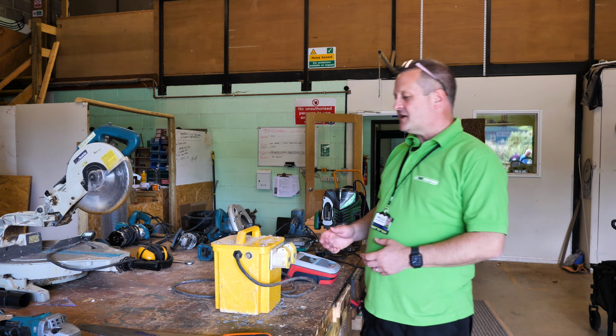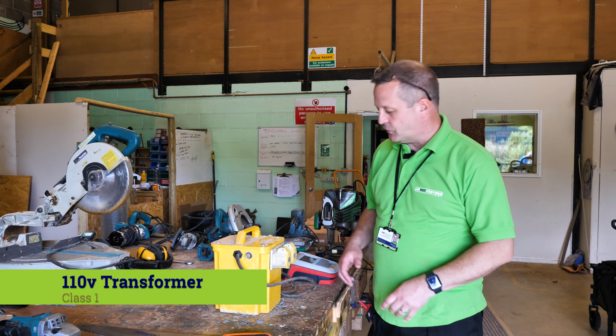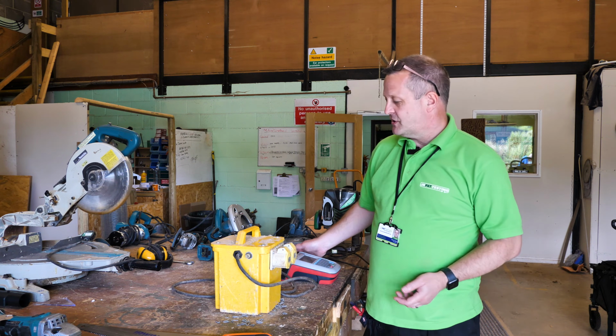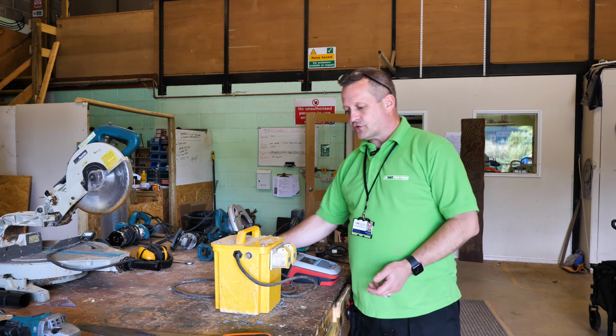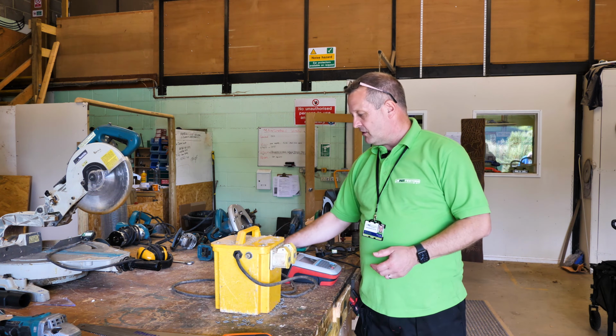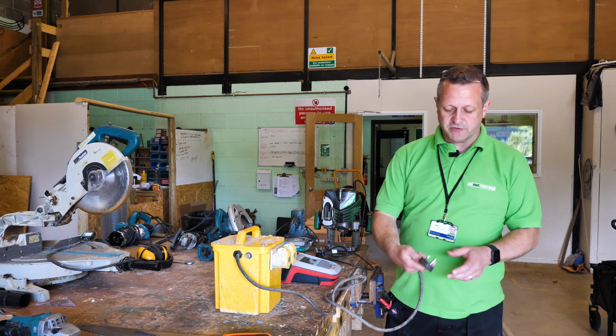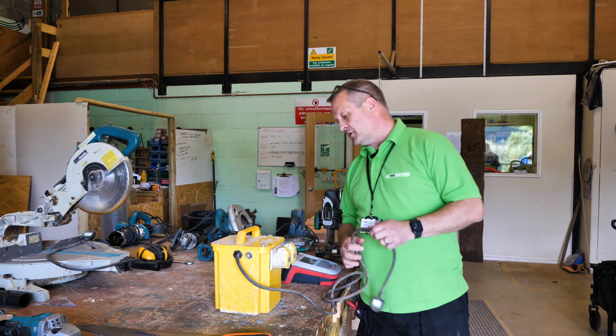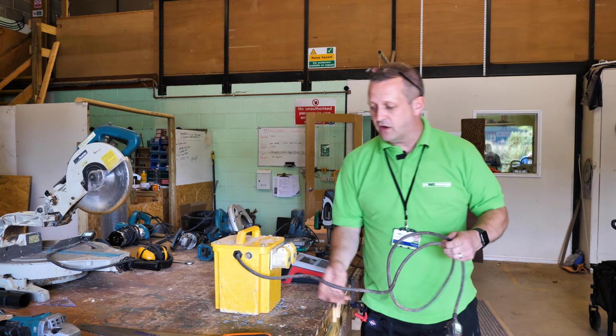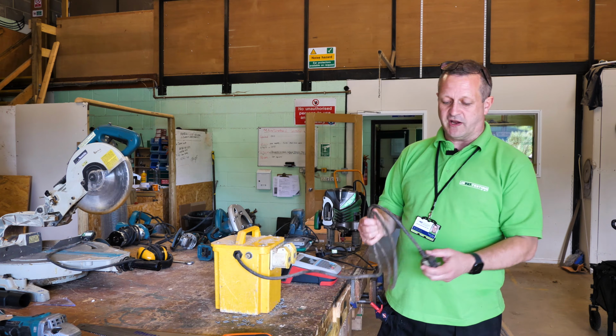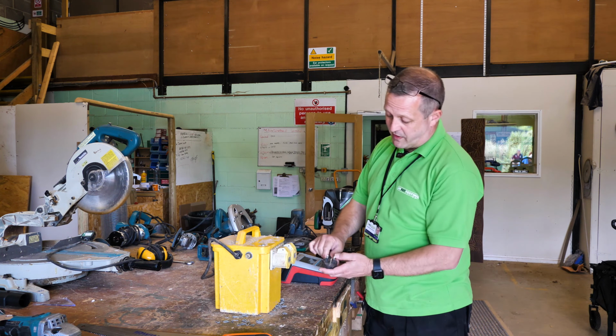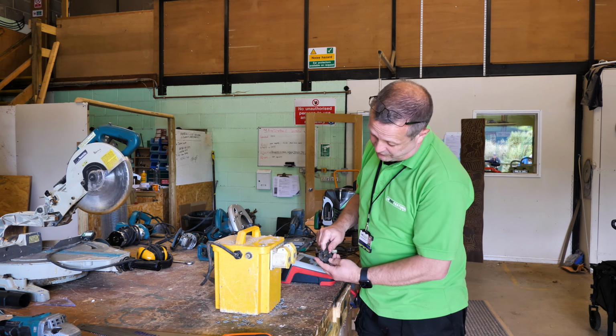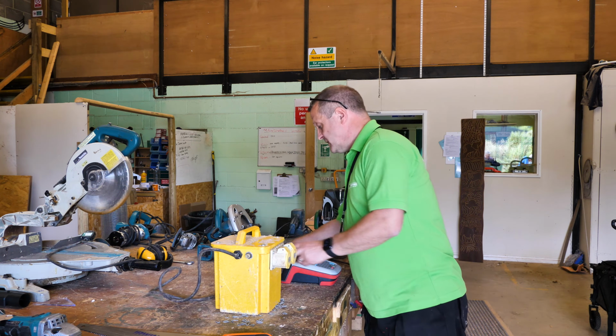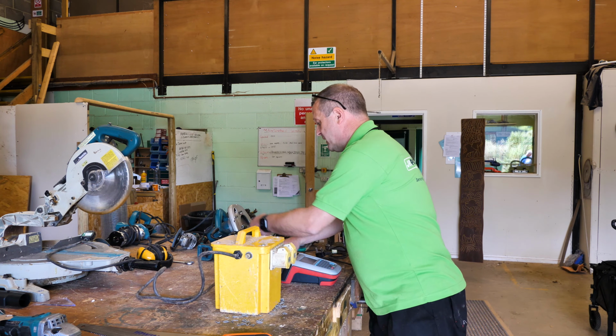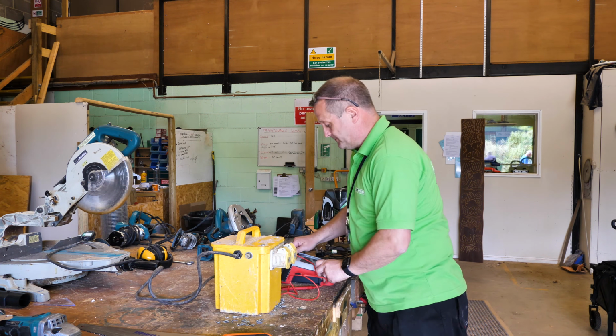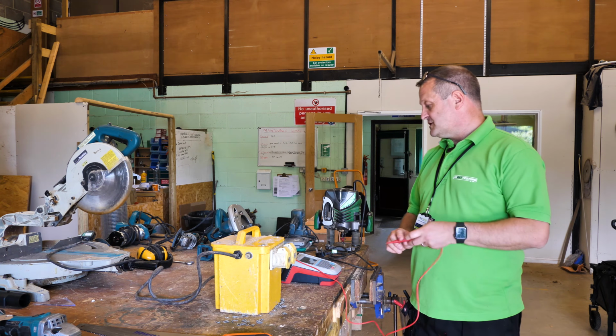So now we're going to be looking at testing a 110 volt transformer. Sometimes these can be a little bit difficult to get an earth reading from. So I'm just going to show a little tip that I've picked up on how to do this. So first of all, again, as with any piece of equipment, we're going to be doing a visual inspection of the appliance. Mainly just checking the cord to make sure there's no cuts or any copper exposed. And we're going to be checking the correct fuse rating for the appliance.